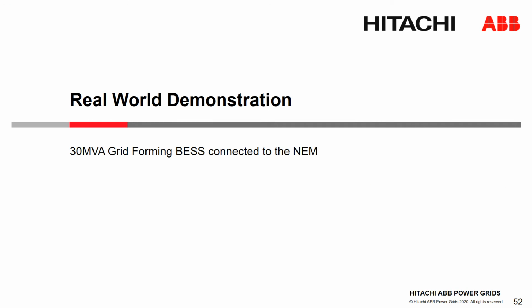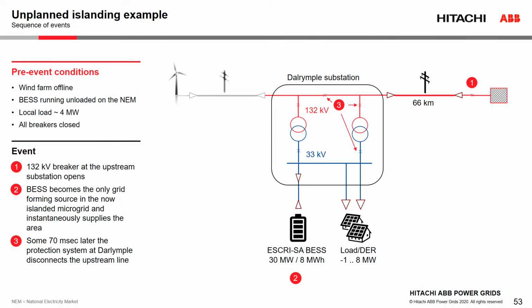So to characterize the behavior of grid-forming converters or virtual synchronous machines, we will look at a real-world example. Here we will look at a sequence where a grid-forming energy storage system is operating in parallel with the NEM, and at point 1, the 132 incoming line protection opens, and then at point 3, the local substation protection opens, forming an independent island with the grid-forming converter and local loads.